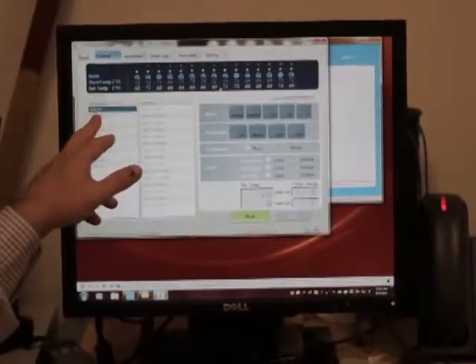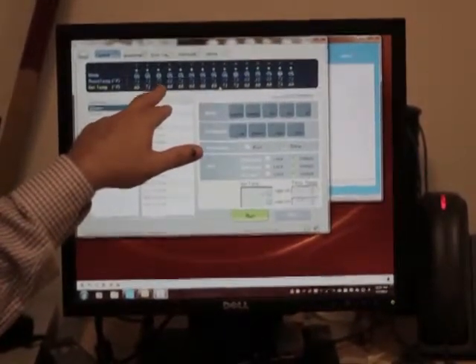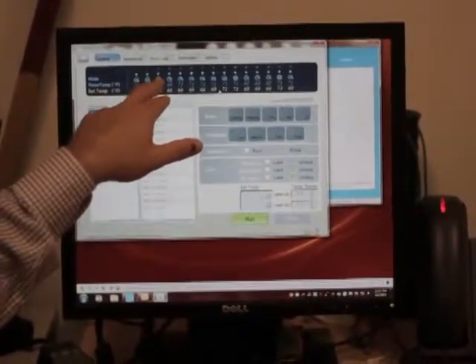I'd like to talk a little bit now about how we control this entire system. One of the important things that we started out on our journey of creating this building was to have state-of-the-art technology that allowed us to control all the building components. We're looking here now at our Andover Continuum system, which allows us to look at the building entirely, what the mechanical systems are doing. So if we were to look at this right now, for example, we know in Group 1 that Section 3 is running, the room temperature is at 77 degrees, the set point is at 68 degrees, and it's in cooling mode.